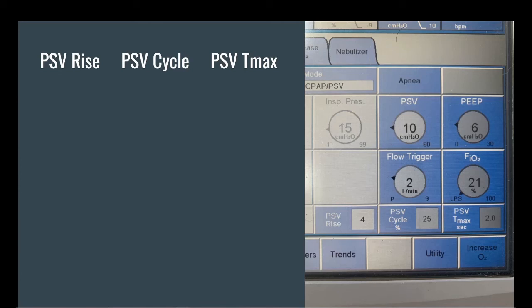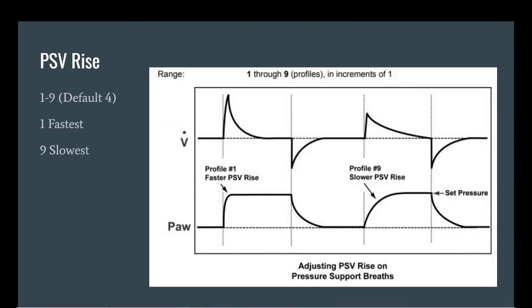PSV Rise control selects the inspiratory rise time profile for pressure support, for PRVC, and for spontaneous breaths. The rise time profiles are numbered 1 through 9, where 1 is the fastest rise time and 9 is the slowest rise time. Starting with the fastest, we can look at profile 1. We can see it's a faster rise, whereas if we look at profile number 9, it is a much slower rise. For each increment, it is approximately 33% longer than the previous one. The rise time settings take effect on the next pressure support breath.